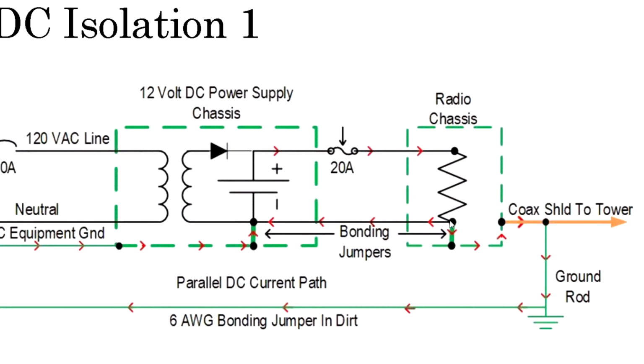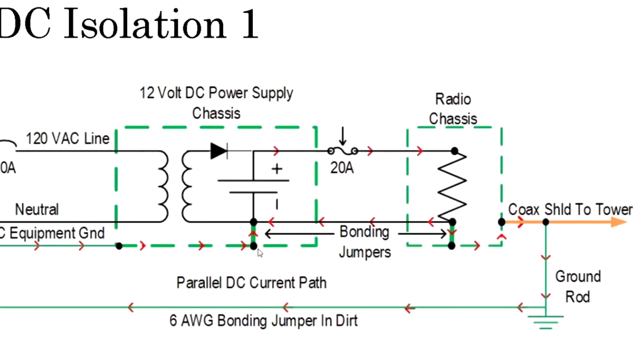The one is the intended and planned path, the black wire that we ran back to our power supply. But the second direction is out the coax, back to the bonding jumper, through the dirt. It comes back up out of the ground, and it heads right to our AC panel box, and then onto our AC equipment ground that we ran out to our wall socket, back onto the chassis of the DC power supply, finally back to negative.